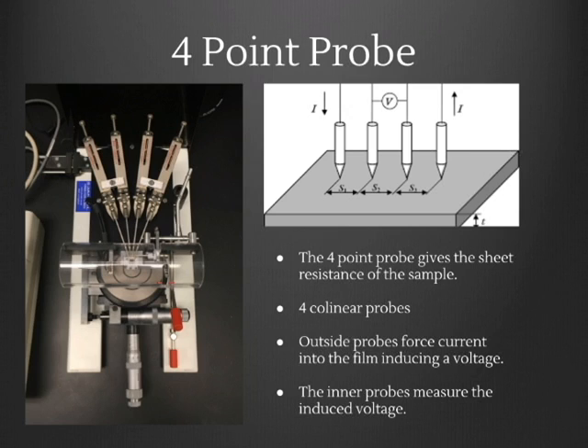When aligned in this geometry, the voltage and resistance effects from the contacts is negligible, giving very high accuracy reading without having to correct for anything. To start, the four probes are pressed down onto the sample. The two probes on the outside, as shown in the figure, supply a current as a source and drain pair, which induces a voltage on the sheet. The inside pair of probes measure this induced voltage and thus the sheet resistance is calculated.